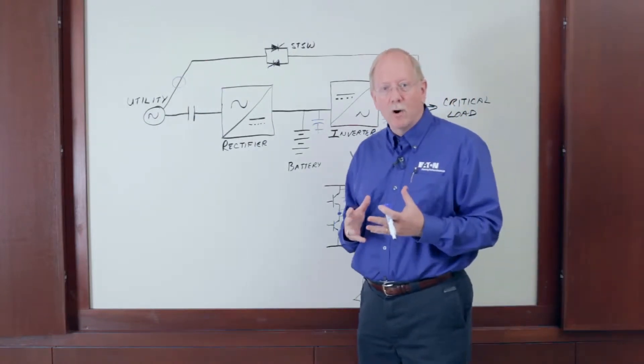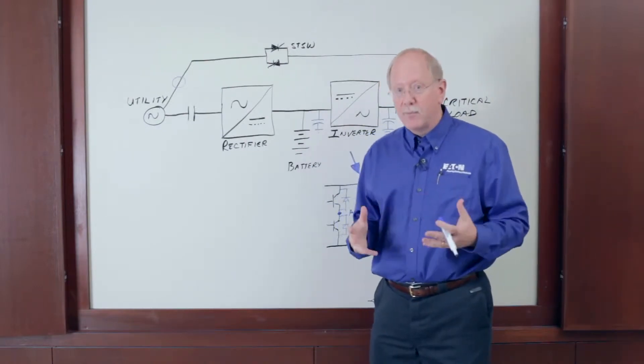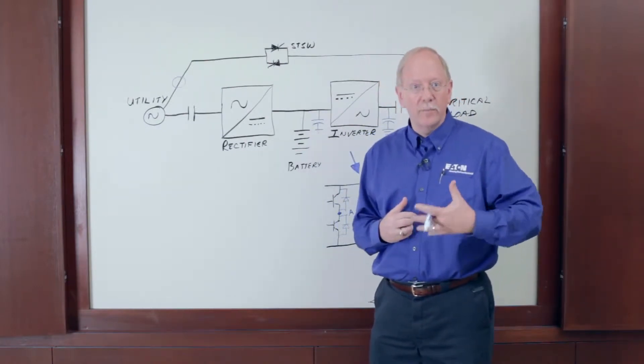So in traditional ECO mode, the plan was to basically turn on the static switch and shut off the UPS. The problem was it takes too long to start a UPS from shutdown mode.